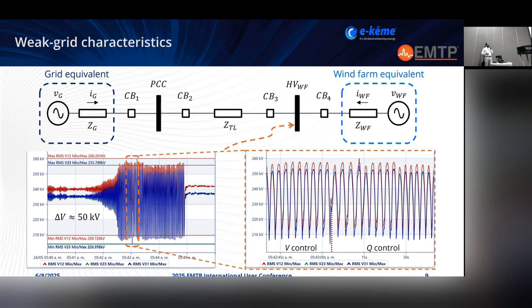So our client informed us that at a certain point in time, around 1 minute after the oscillation started, there was a voltage control mode, and it was ordered to change the voltage control mode to a Q control with a reactive power set point of 0 megavars. So we can see that these voltage oscillations kept going, didn't dampen until about 3 minutes after they started, and it stabilized around this value of 238 kilovolts.